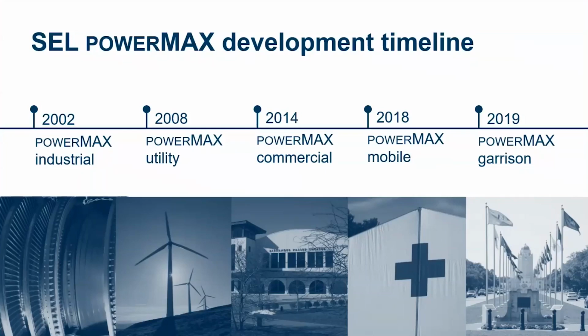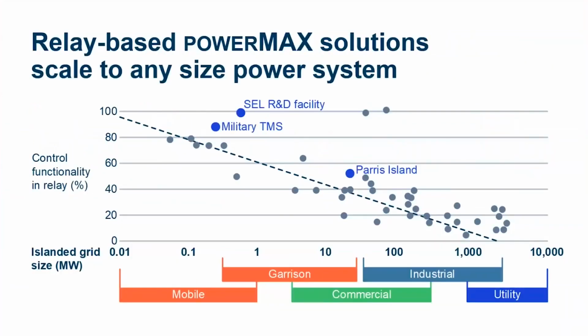For the market in the, again, 1 to 20 megawatt, sometimes kilowatt scale, we've been able to double the features and reduce our prices. And this has largely been accomplished by the plug-and-play technologies and that distributed edge computing that those relays provide us. We've now found that these SEL relays provide a solution that scales from kilowatts to gigawatts. On the vertical axis, you see that as jobs get smaller in size, they move to the kilowatt scale. We push more and more functionality into the relays. This reduces cost and complexity to the size of your project, from one relay to 10,000 relays.